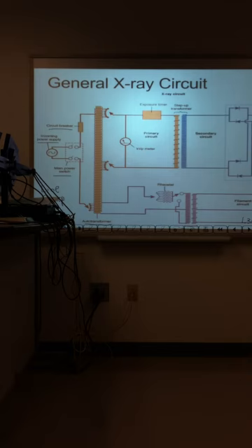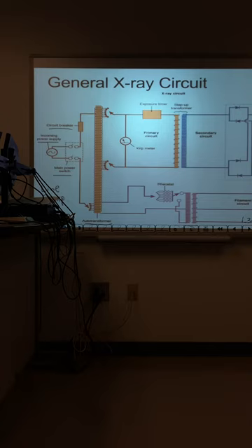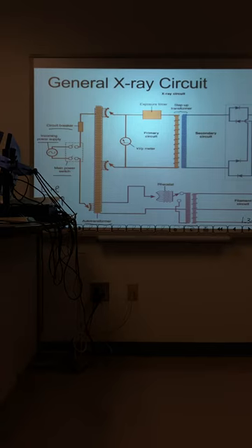As you said, the auto transformer basically regulates kVp. Line compensator, main power switch goes to the line compensator, then to the circuit breaker, then to the transformer. Y'all got it? I'll send you guys this PowerPoint.